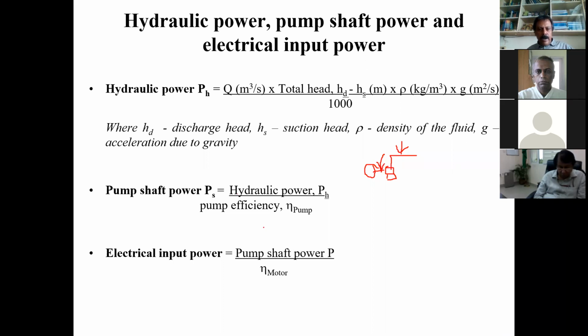That means the power at this point, input power to the pump. So this will be the hydraulic power divided by the pump efficiency. So you can see this. The pump input power or the pump shaft power is hydraulic power divided by pump efficiency. And what is the power drawn? Electric power drawn by the motor itself is the pump shaft power divided by the efficiency of the motor. So these are the simple equations that we'll be using.